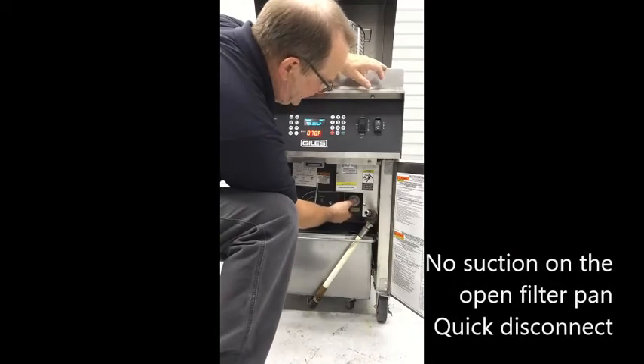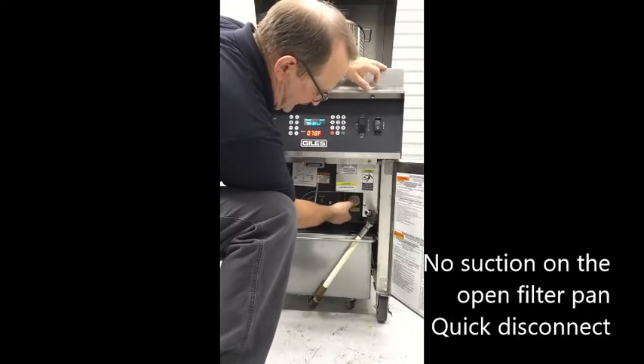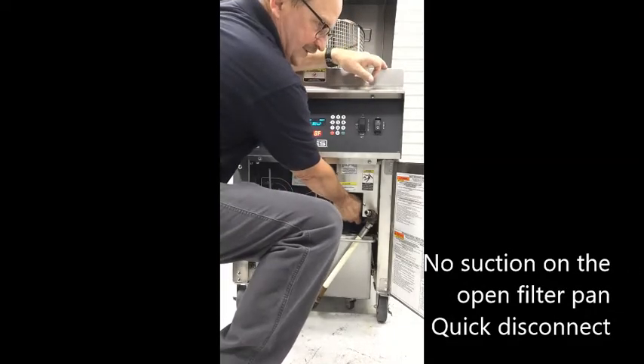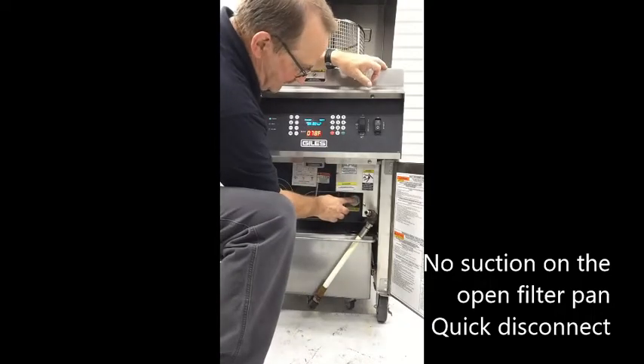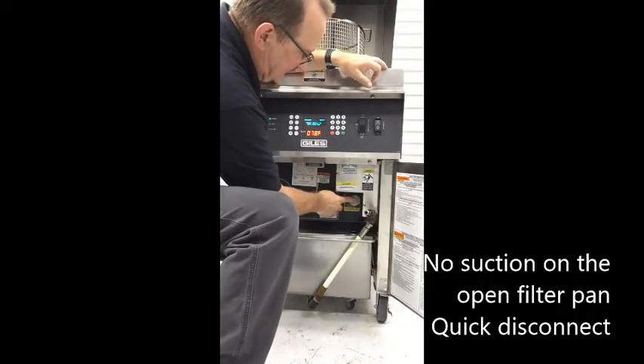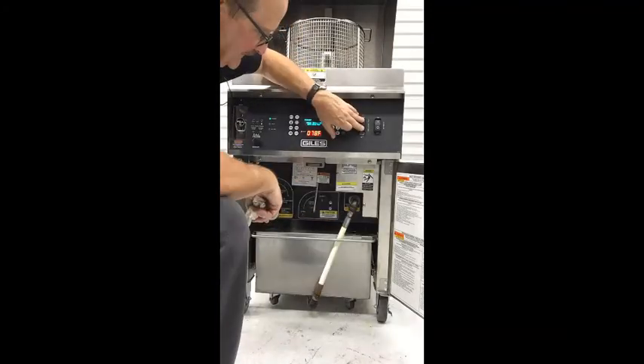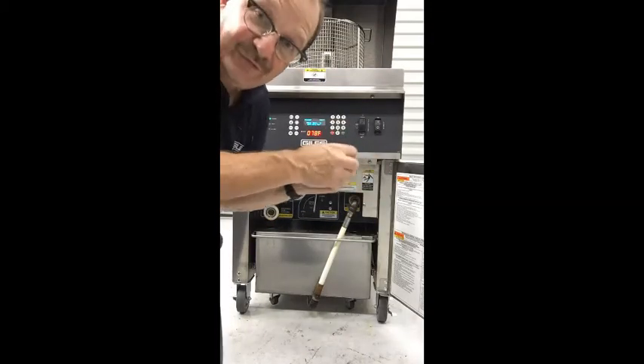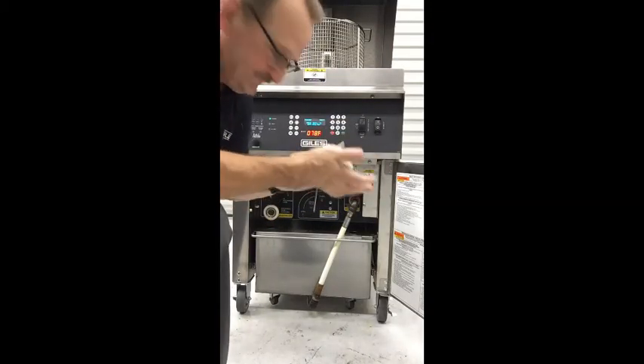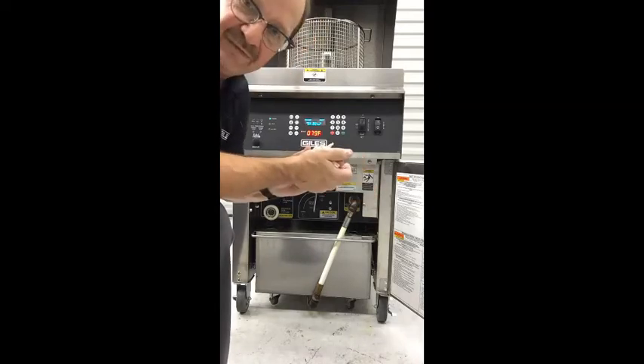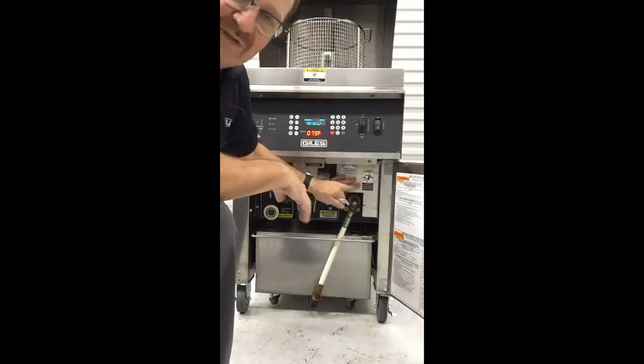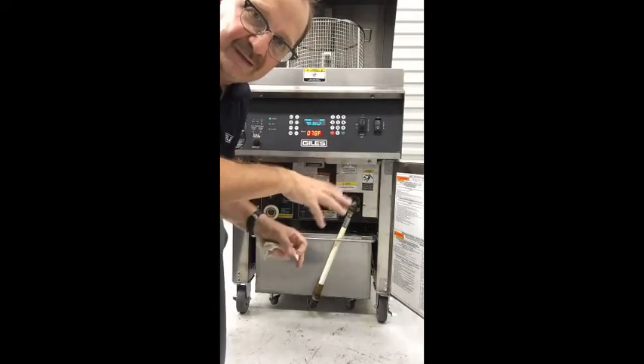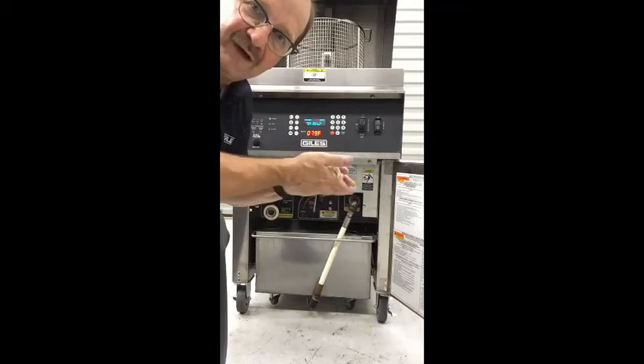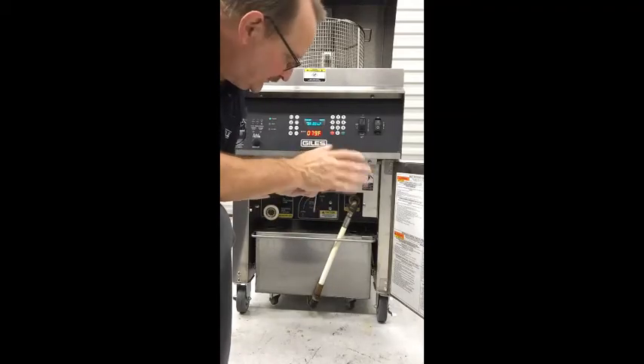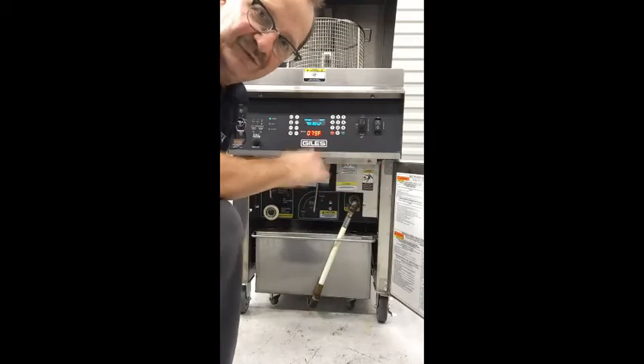And you should feel a suction right there when that pump runs. It's not a huge suction, but you will feel a little bit of a suction right there. Okay? This turns out to be a very good time to talk about the pump itself. If these sit for quite some time, oftentimes that pump will lock up and the pump will not want to run. So what we want to do is go back, take a look at the pump, and see what we can figure out back there.